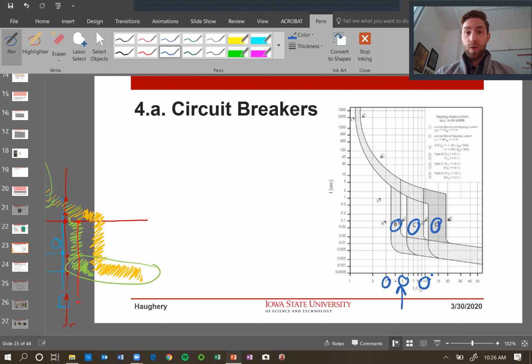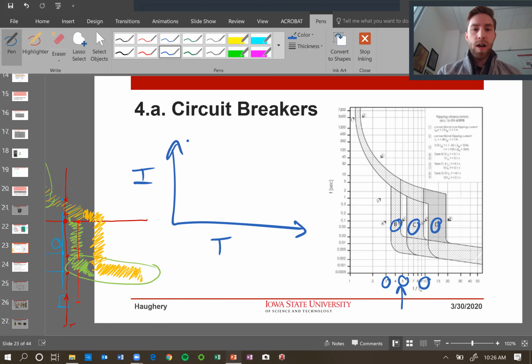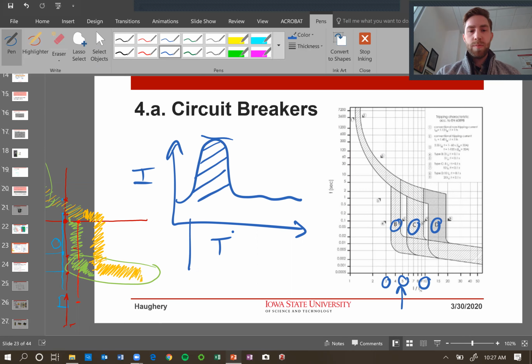And so a lot of times that is a question of inrush current. I have current here, time here, and I know that my motor is going to have this huge inrush current and then this steady state current. I want to get past this high point, and that's a certain amount of time, okay? And so the farther I go this way, the more time I have to withstand that inrush. And that's really a big takeaway. And so we're trying to pick that circuit breaker type based on how long our inrush is, based on how much multiple of the normal current.